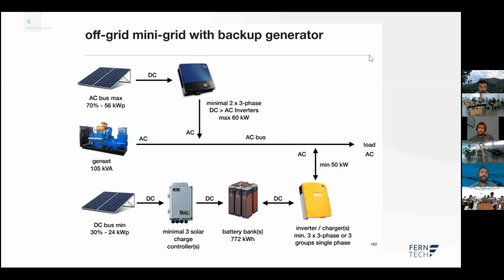So we need 80 kilowatts of PV. If we built this purely on AC coupling, we might probably need maybe 85 kilowatts to compensate for the loss of efficiency charging the batteries. If we build everything 100% on DC coupling, the same - we need to compensate with more solar to compensate for the efficiency on the daily consumption.